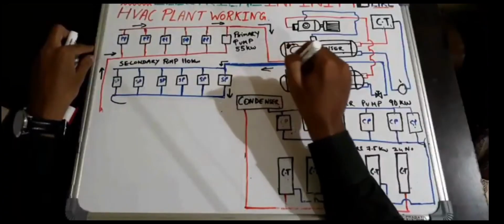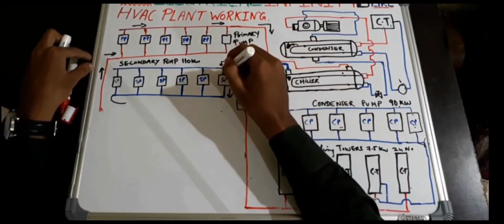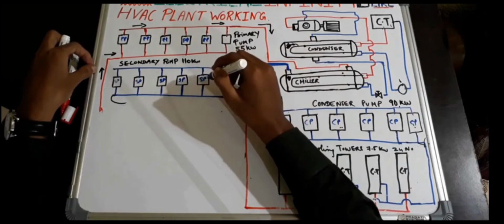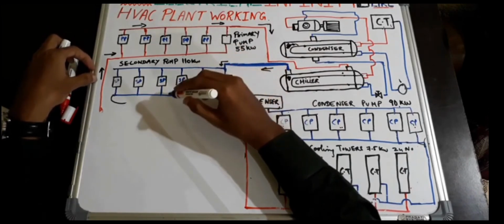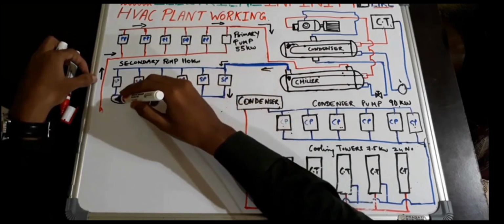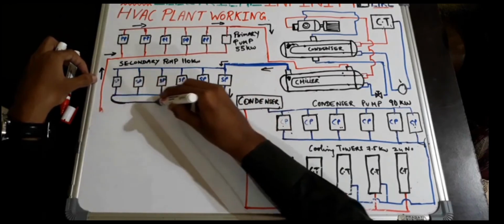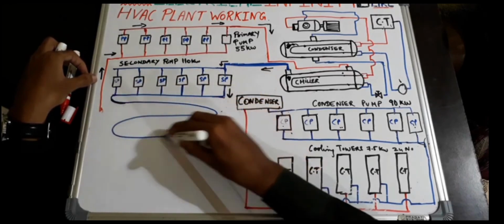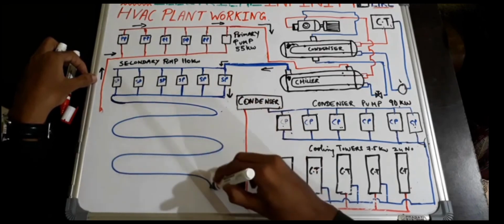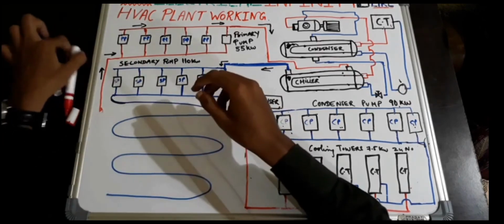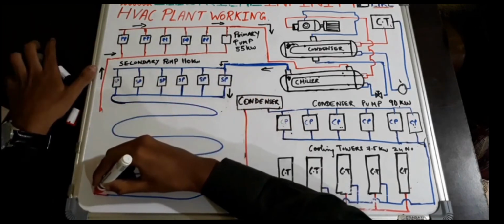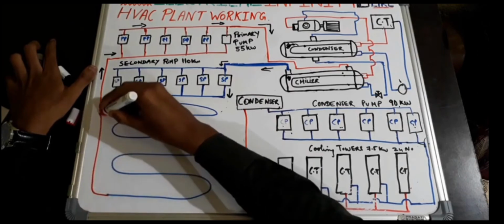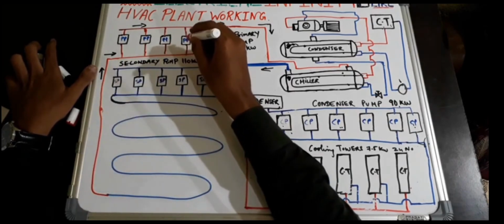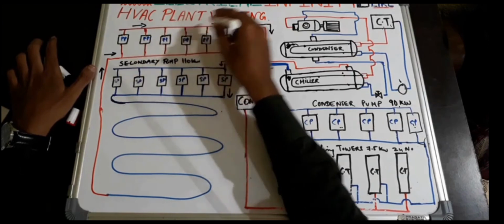The chilled water from the chiller, as you can see here, is sent to the secondary pumps of 110 kilowatt each. Here we are using 6 secondary pumps of 110 kilowatt. From the secondary pump, the water is circulated to the entire building for cooling. So this is a 7 floor building, and after cooling the air of this building, the water gets heated up, and this high temperature water is pumped back with the help of the primary pump, as you can see here, and is sent back to the chiller.